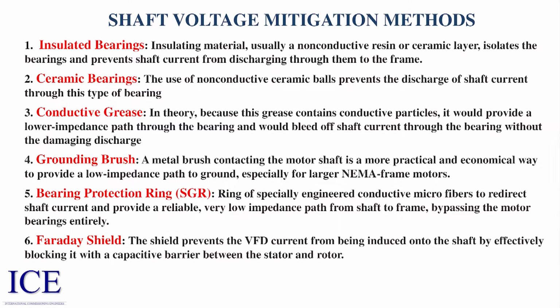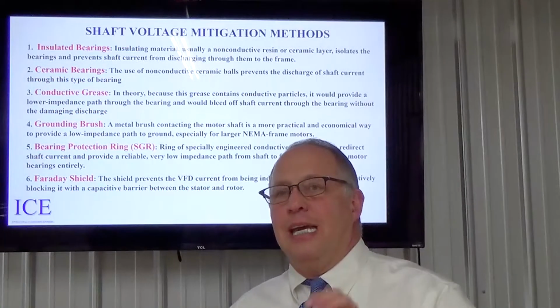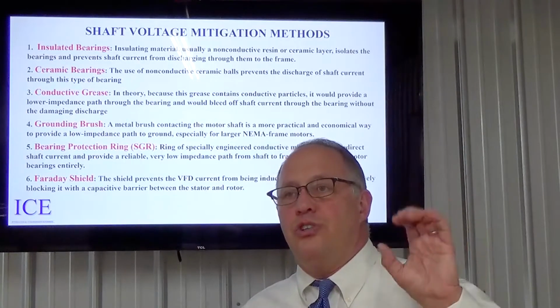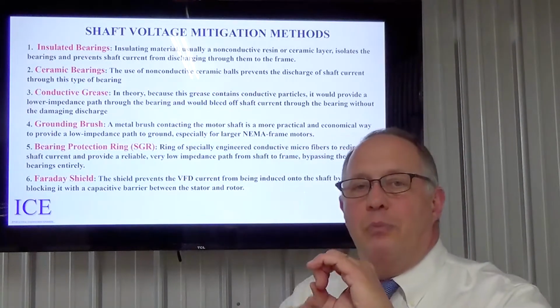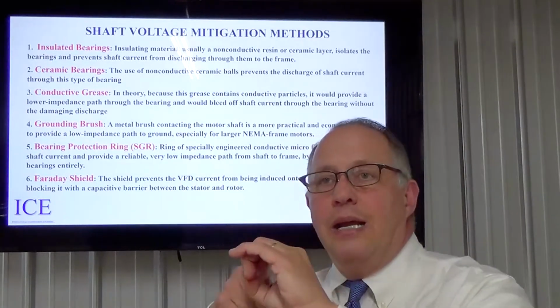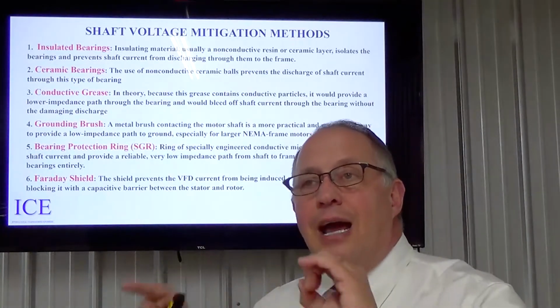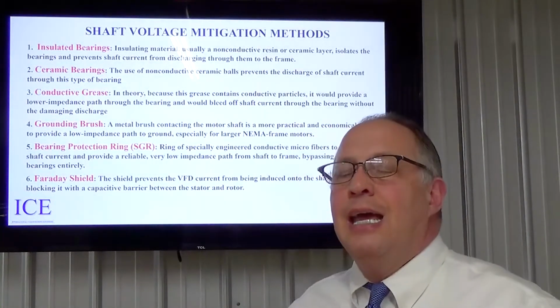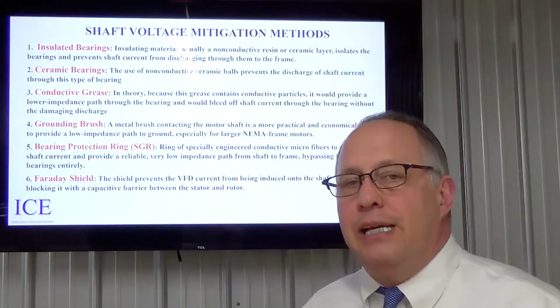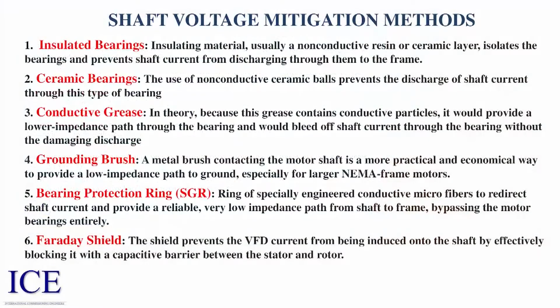shaft grounding ring. Rings with specially designed, engineered conductive microfibers redirect the shaft current, providing a reliable, low impedance path from shaft to frame, bypassing the motor bearings entirely. Once again, here the fibers are tied to the shaft itself, on the ring or on the shaft, and they're actually tied to the motor housing, and that provides a path to bleed off any induced voltage.